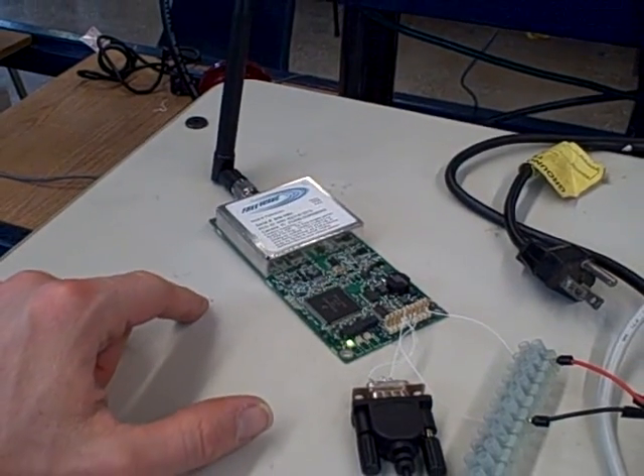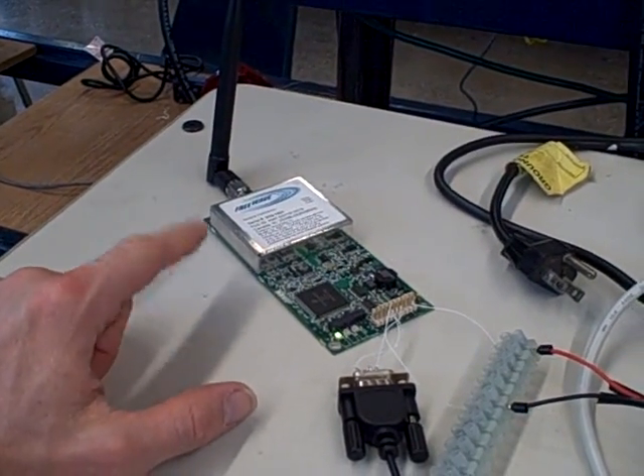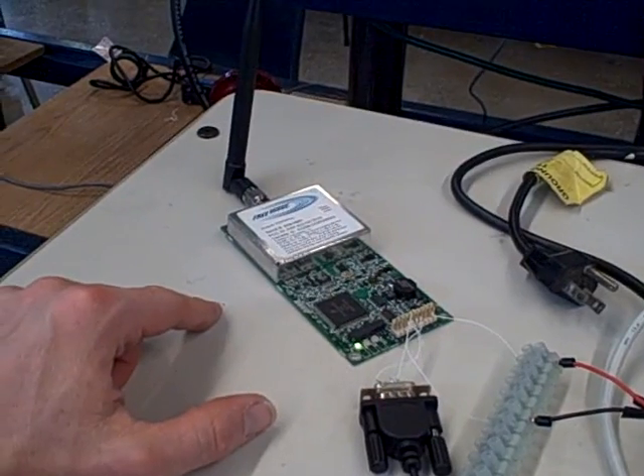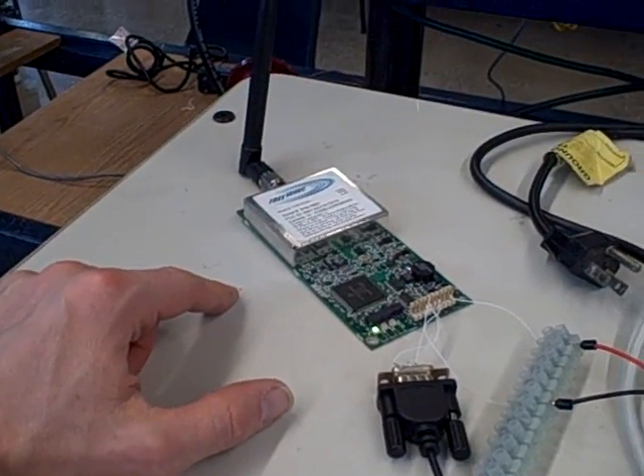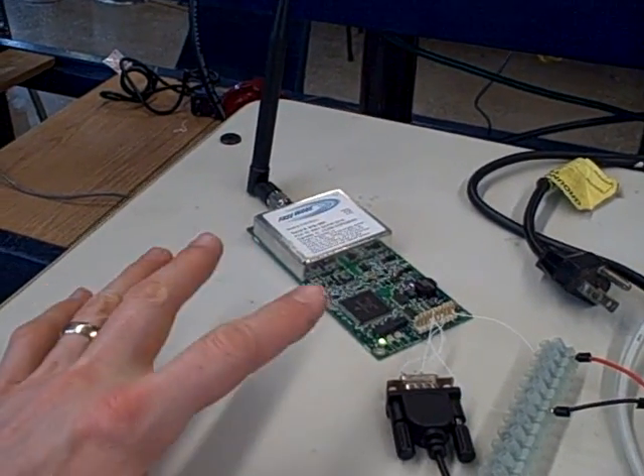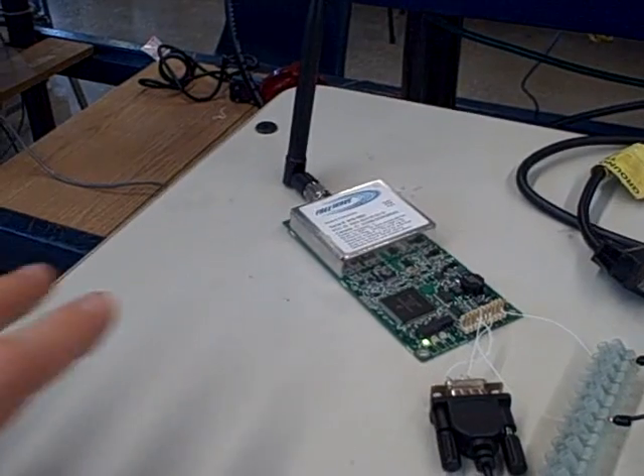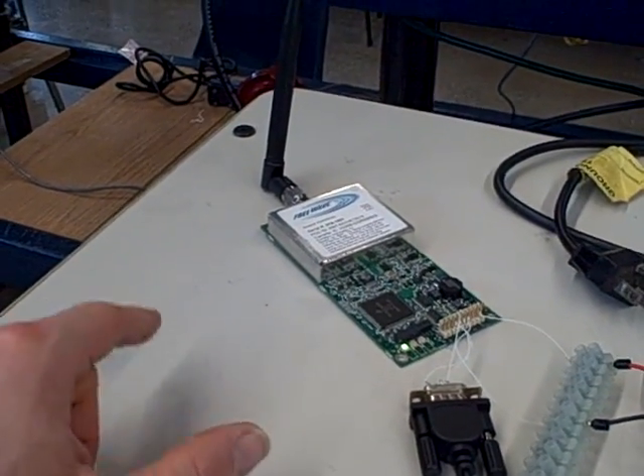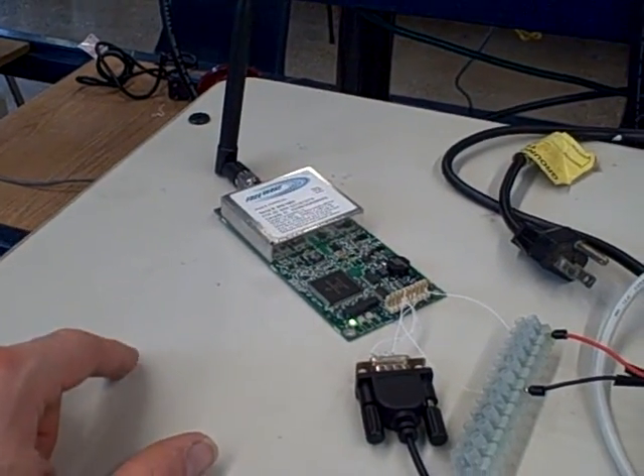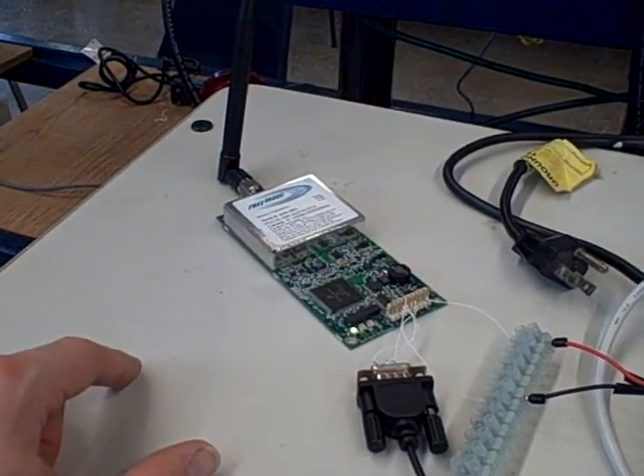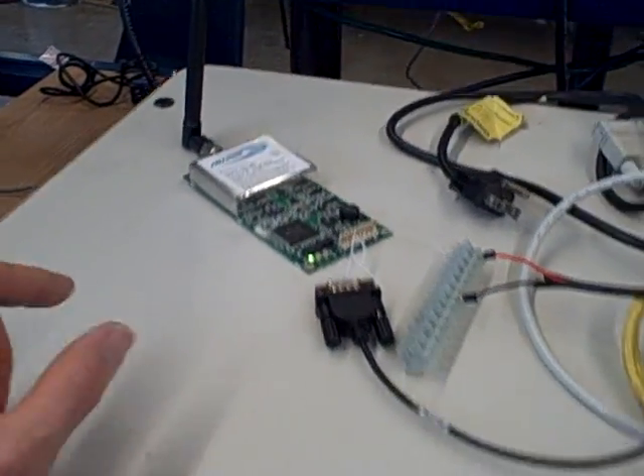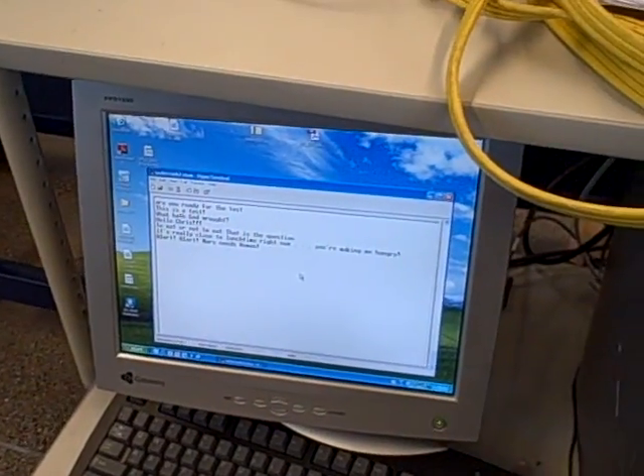These FreeWave units are much nicer. They have more power, they have more diagnostics capabilities, and most importantly, they have the ability to do a multi-point network, which is more than just point-to-point, more than just two units. We can have several units out there with one master and multiple slaves. So that's the kind of upgrade we're hoping to do to the SCADA system. And this is the test that we did it with.